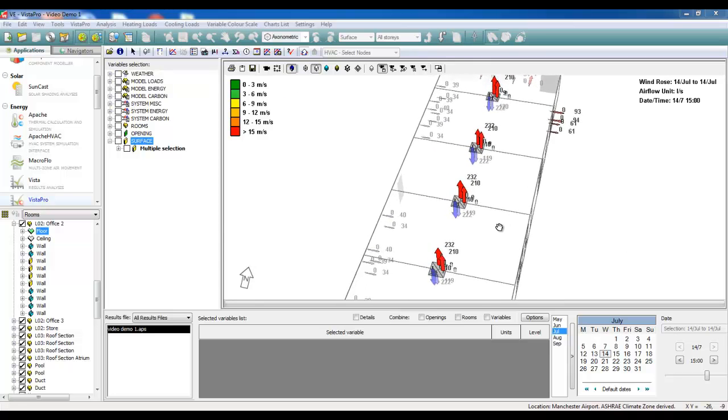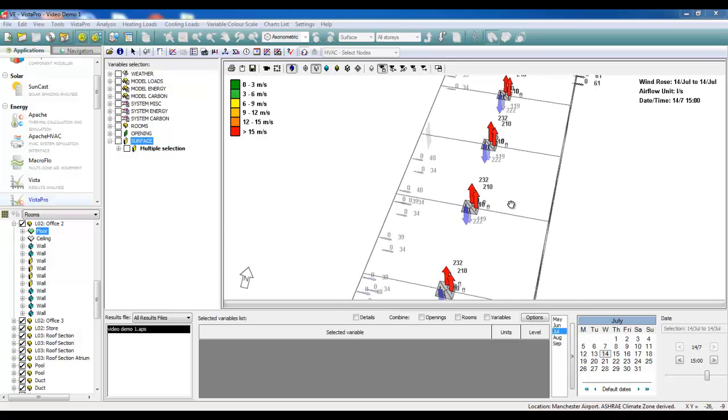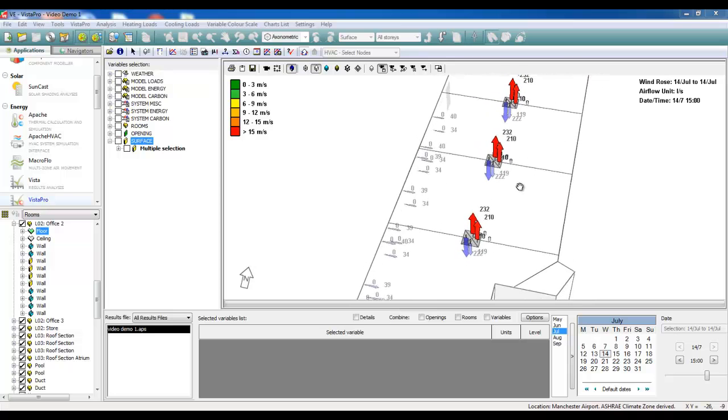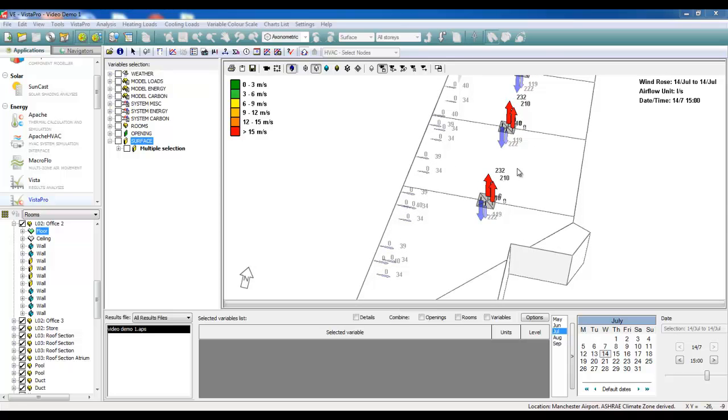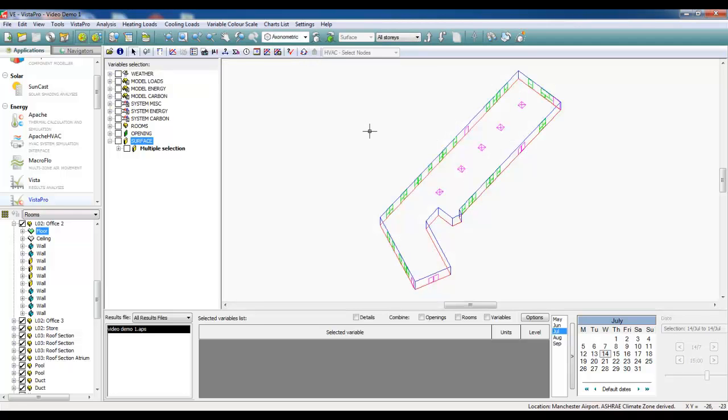we can see that those quadrants with the blue arrows are upwind. Therefore, the wind is being channeled down through the wind catcher into the room, and those represented by the red arrows are extracting because they are downwind, under the quadrant where the negative pressure is experienced. This gives us a huge amount of confidence in the fact that IES is replicating the performance of wind catchers as we would expect.